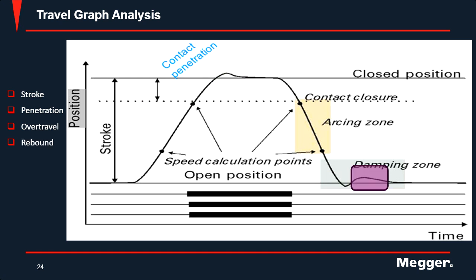You have a rebound. As you can see, we had a little overtravel there. And because of that, it rebounded back up inside that dampening zone. It is measured from the minimum displacement after the maximum displacement of overtravel to a final resting place. So basically, it's just vibration after that overtravel. It overcompensates, rebounds up past the steady state, and then comes back down to steady state.